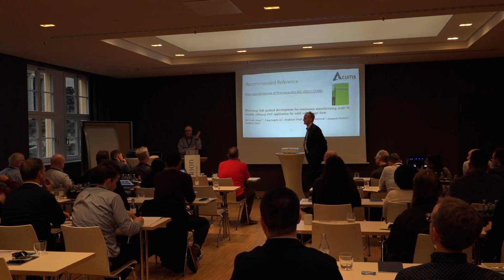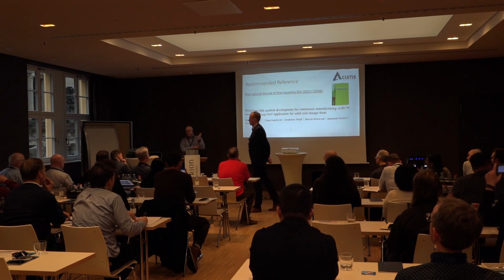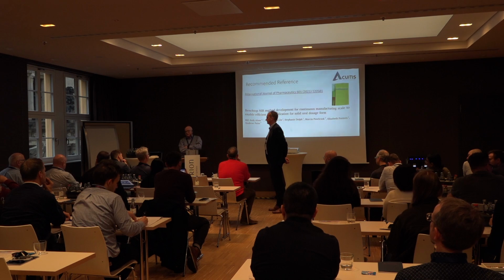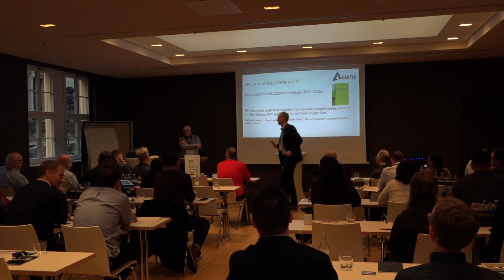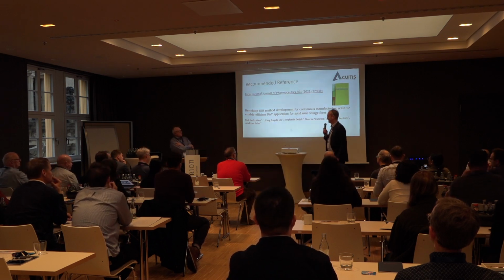It's to prevent outliers. I'm a firm believer that if you can engineer out any disturbance in the spectroscopy, basically using engineering solutions rather than chemometrics, that's what I do. So that notch means that there is always at least a millimetre of powder between the metal surface of the finger and the probe tip, because if diffuse reflectance probes shine light down onto bare metal, you get a big bolt of light coming straight back in, and it adds noise to the spectra. So it's better to engineer out that effect than try to remove it by chemometrics. But the outlier rejection system in the Sentronic software will do that. Exactly. And it's not chemometrics.